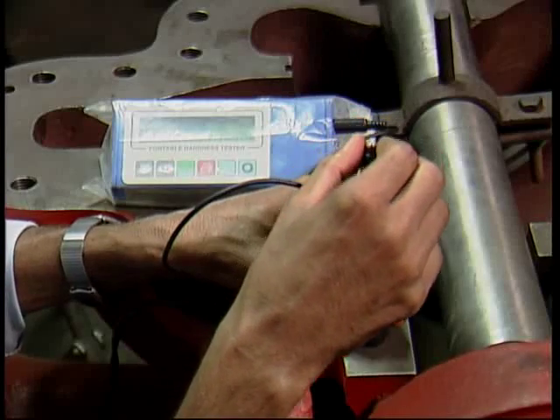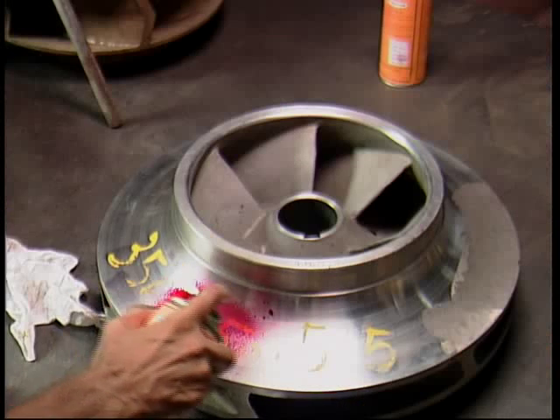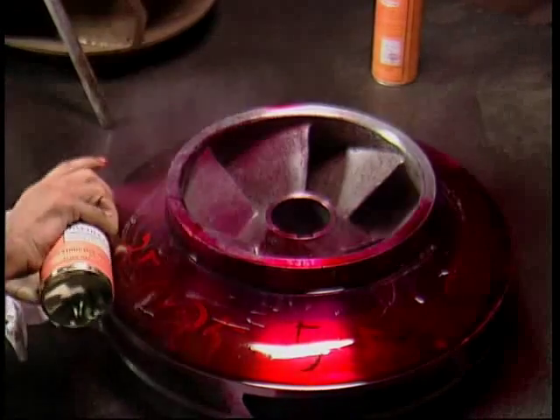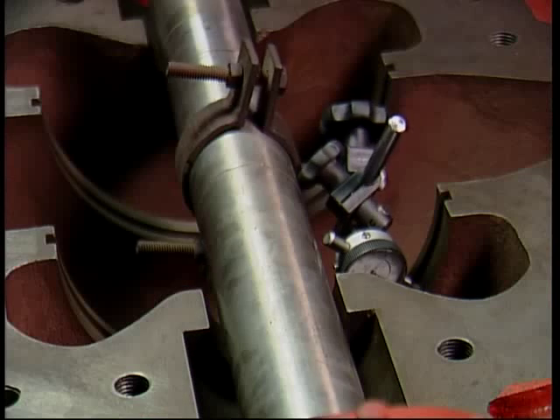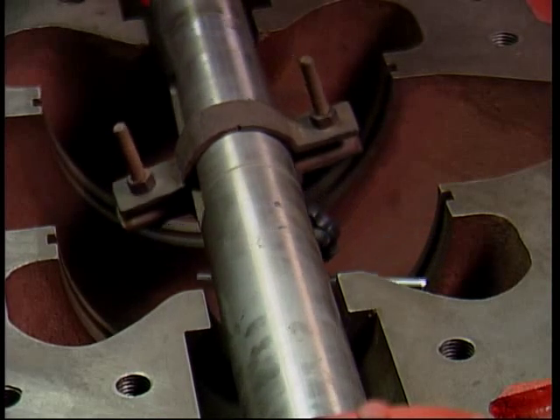Random checks on casing hardness are carried out during pump assembly. Dye penetrant test is done on all critical impellers and casings. Here we are checking the concentricity of the stuffing box and neck ring bores.